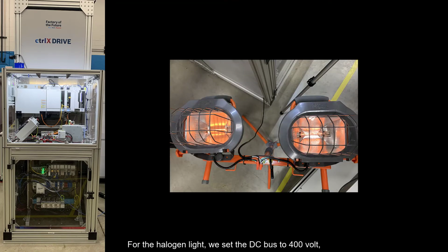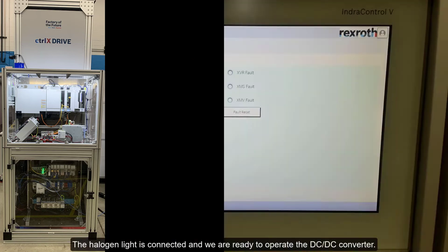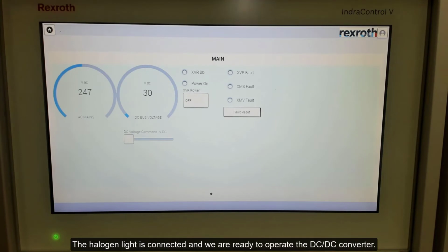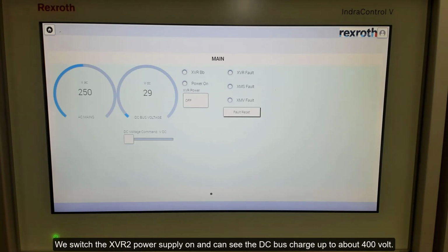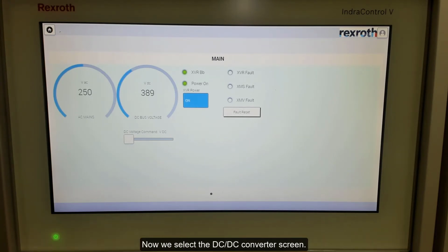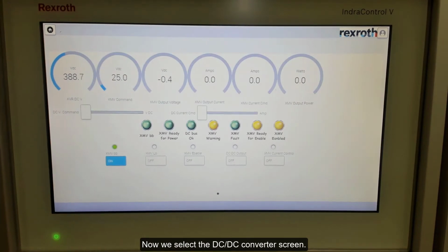For the halogen light, we set the DC bus to 400 volt and allow a DC output voltage between 20 to 250 volt. The halogen light is connected, and we are ready to operate the DC-DC converter. Since the halogen light is for 230 volt, we can leave the DC bus to around 400 volt. We switch the XVR2 power supply on, and can see the DC bus charge up to about 400 volt. Now we select the DC-DC converter screen.